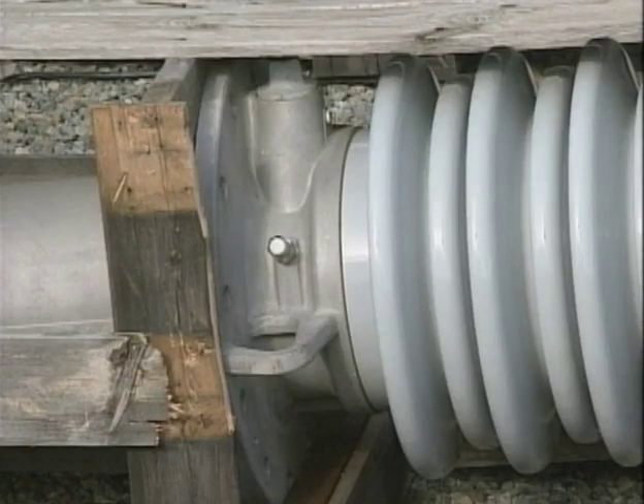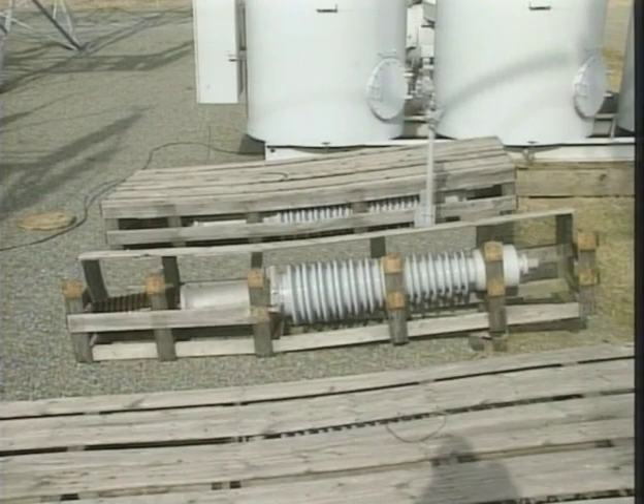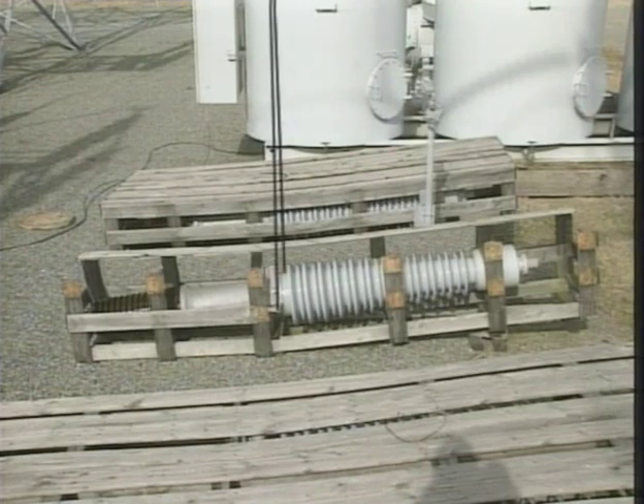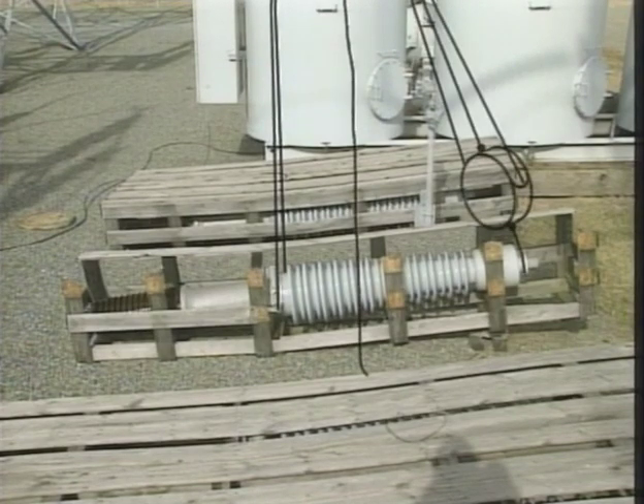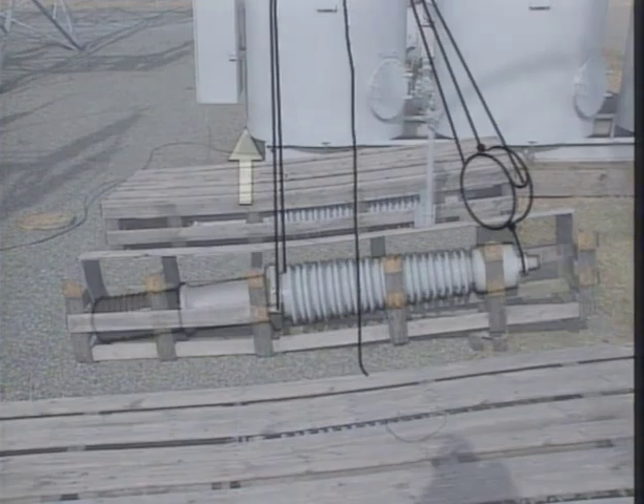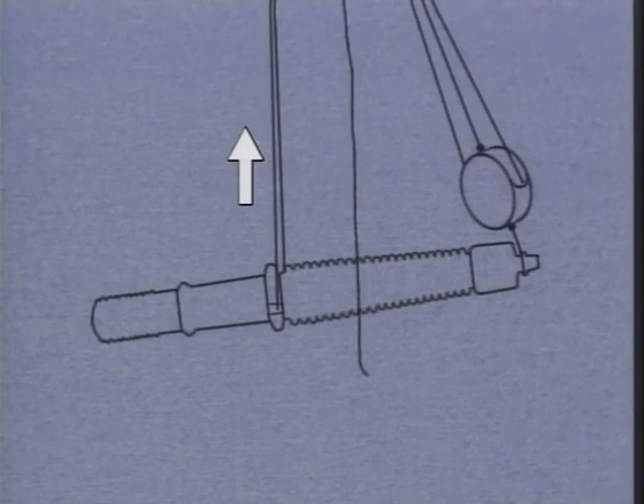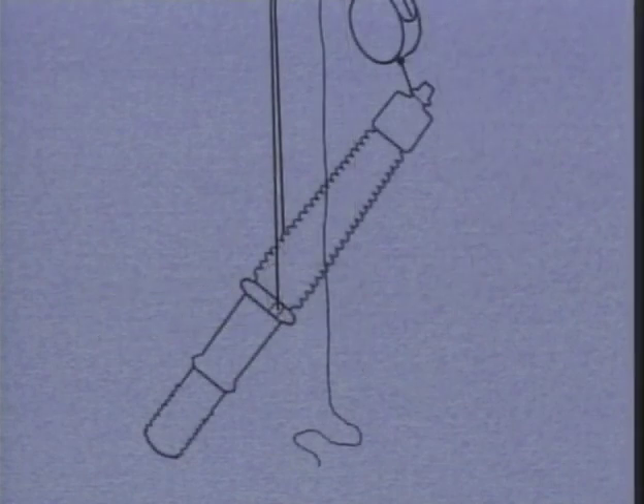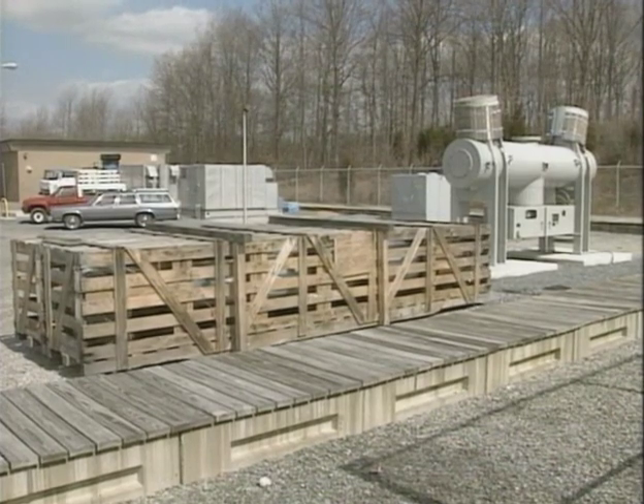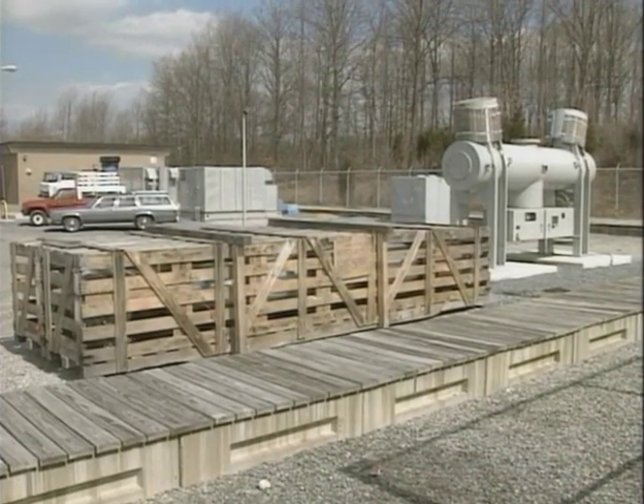Each bushing contains a mounting flange with lifting loops on opposite sides of the bushing. To lift the bushing and install it in the breaker, slings are attached from the lifting hook of a crane to the lifting loops on the mounting flange of the bushing. In addition, a block and tackle is connected between the top of the bushing and the lifting hook of the crane used to lift the bushings. The bushing is lifted clear of the crate using the slings. Then the block and tackle is adjusted to give the bushing the proper tilt so that it can be easily inserted into the breaker.